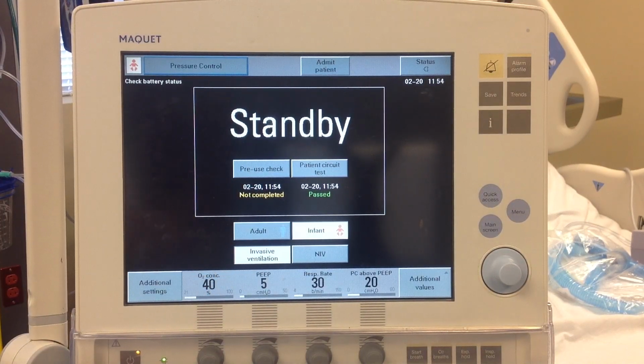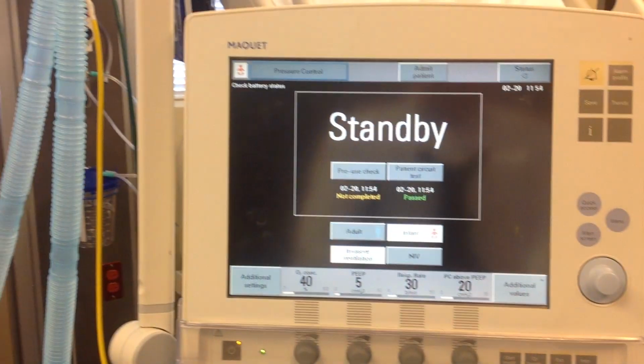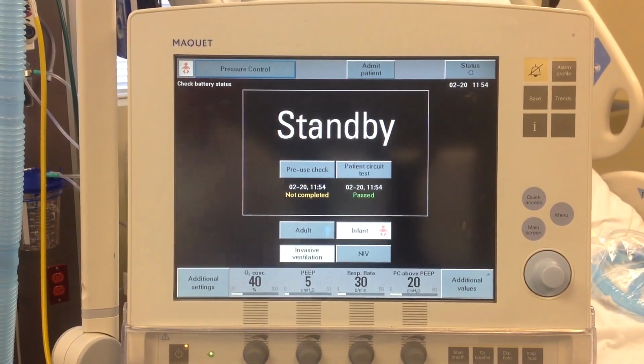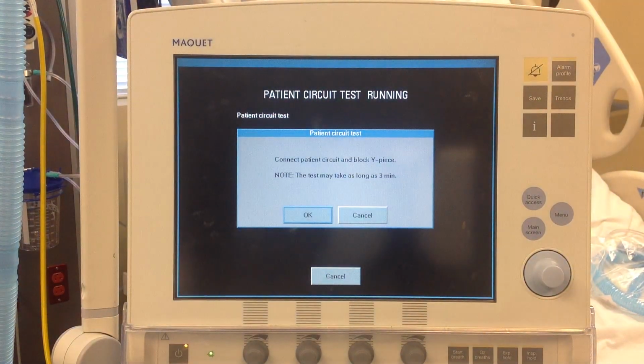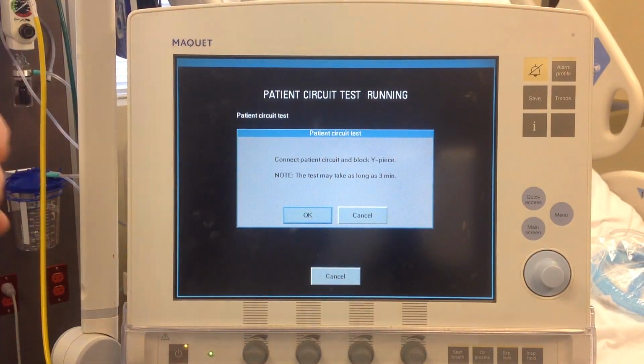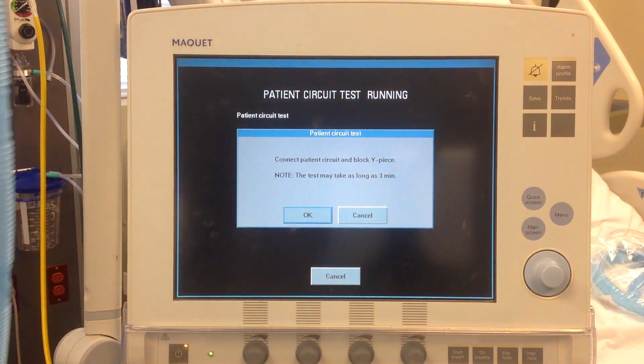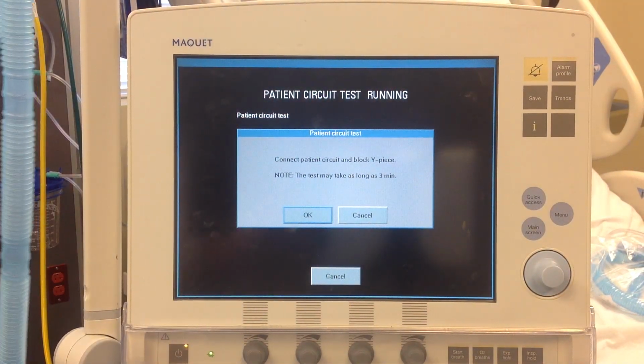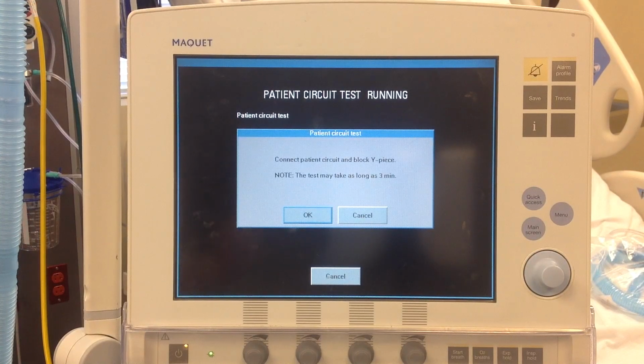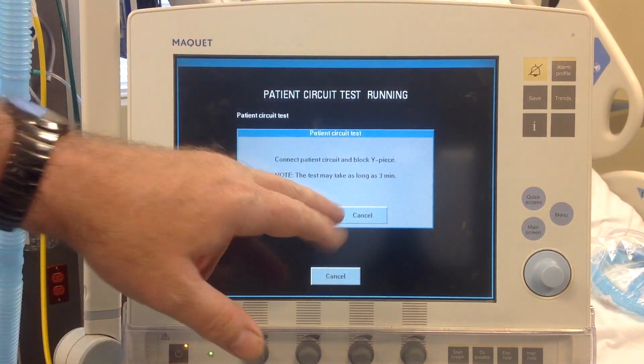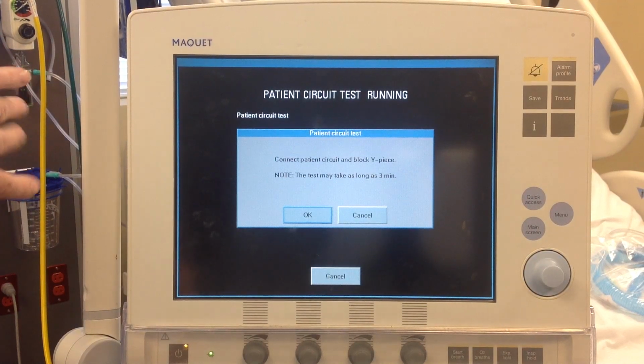Now, I told you I'd show you how to redo it. So let's say you switched your circuit. Your circuit right there. If you switched your circuit and needed to replace the circuit, all you would do is patient circuit test, and there it goes. Connect patient block Y. This would be the brand new circuit that you put on. You replace the circuit, replace it with a heated wire, went from adult to pediatric, adult to neonate, or just change the circuit, period. Because you change the circuit, anytime you switch it, you'll want to do this.